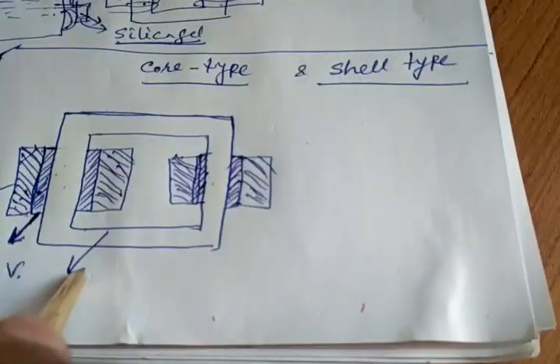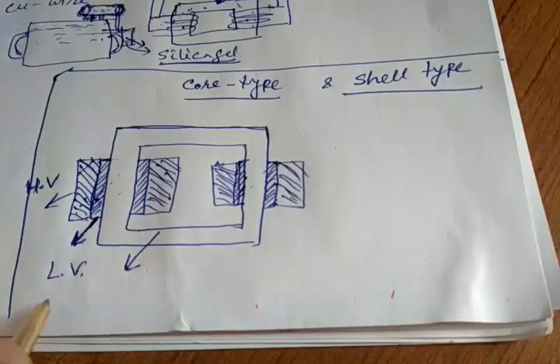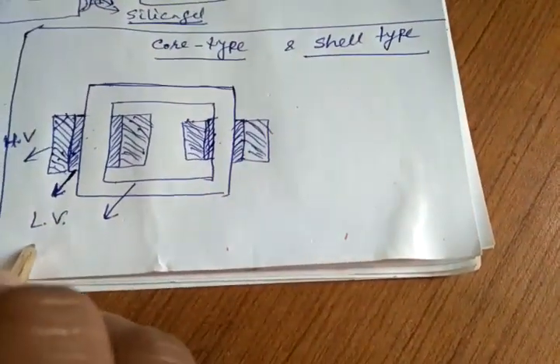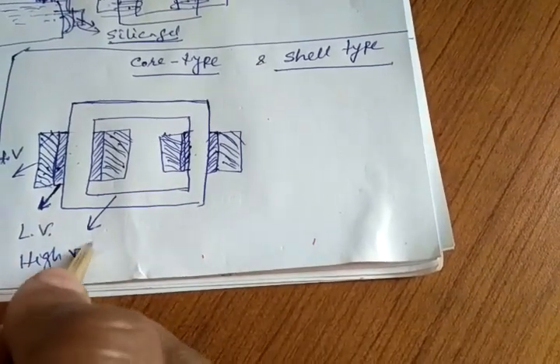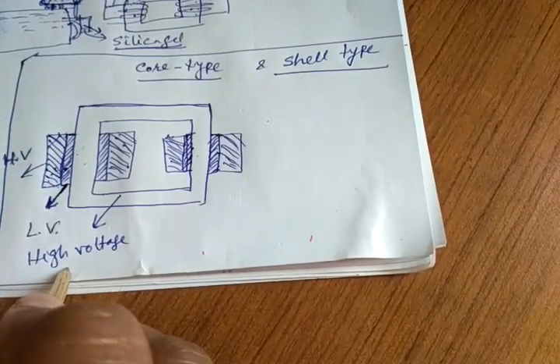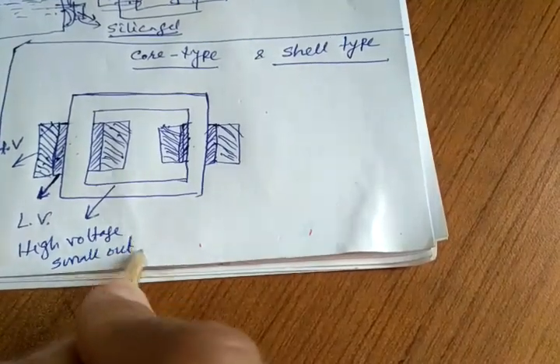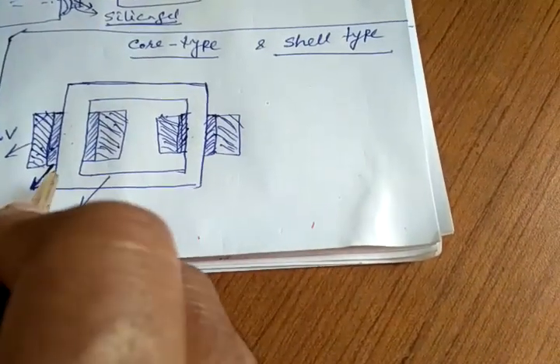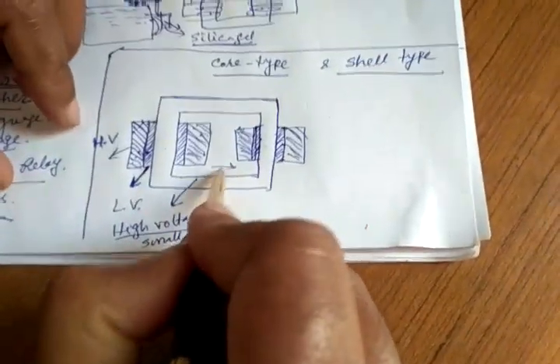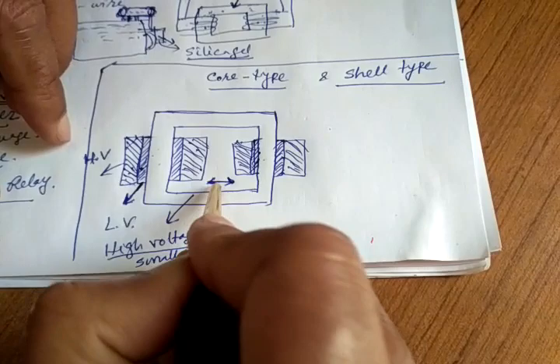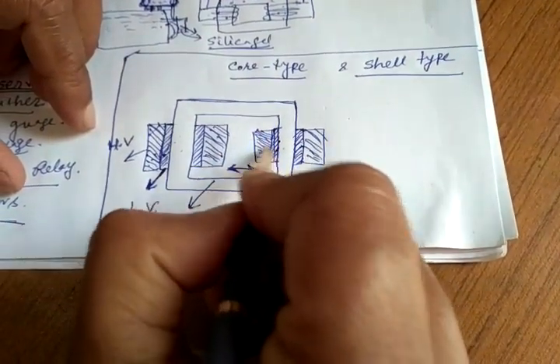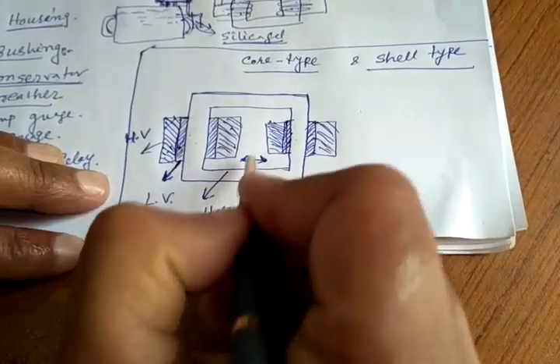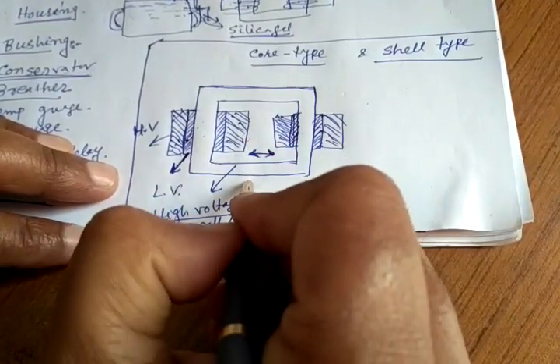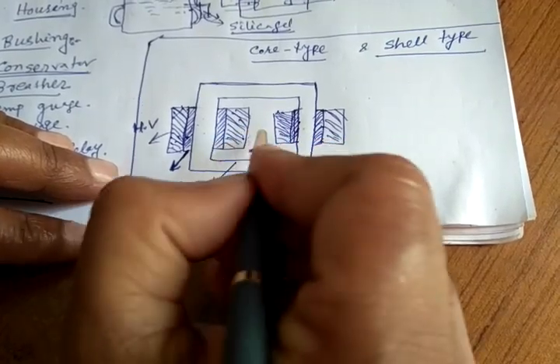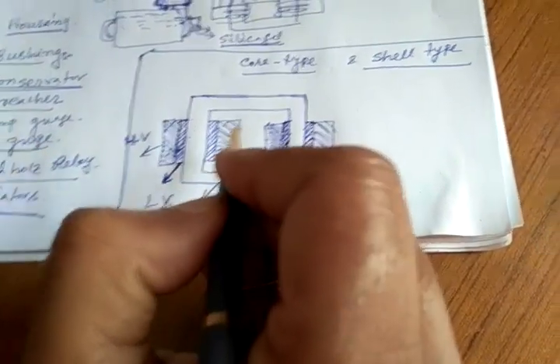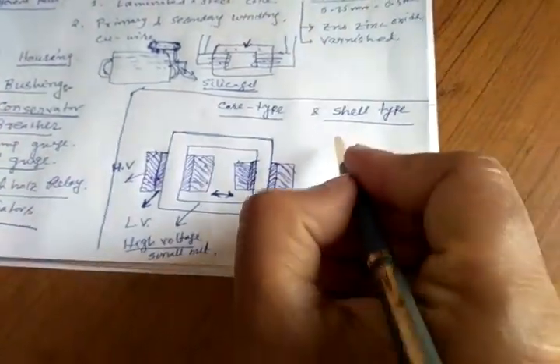And these core type transformers are normally used mainly for high voltage, when the secondary voltage is very high but the output is small. The kVA rating is small, but the secondary voltage is very high, because this portion is high voltage, so this portion provides higher insulation. And one more important advantage is that it could be air cooled, because there is a lot of gap, so air could pass through this, and this air could take out the heat generated in the windings. So in that way, it is helpful when we compare it to the shell type.